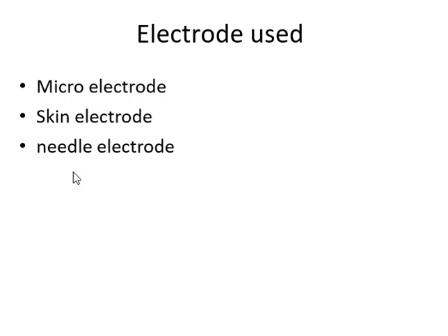Needle electrodes are of different types: single fiber electrode, concentric electrode, monopolar electrode, macro electrode. Needle electrode is made of stainless steel. The monopolar needle electrode has a very finely sharpened point and is covered with Teflon or other insulating material, except for a 0.5 mm exposed tip. The advantages of the needle electrode are ease of use, low impedance, and stability.